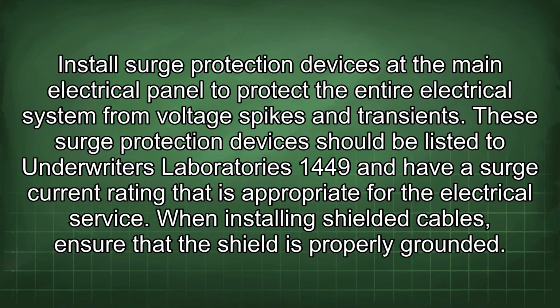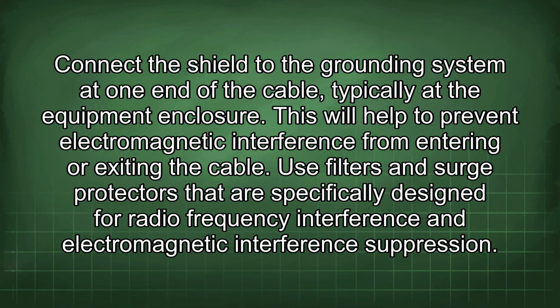When installing shielded cables, ensure that the shield is properly grounded. Connect the shield to the grounding system at one end of the cable, typically at the equipment enclosure. This will help to prevent electromagnetic interference from entering or exiting the cable.